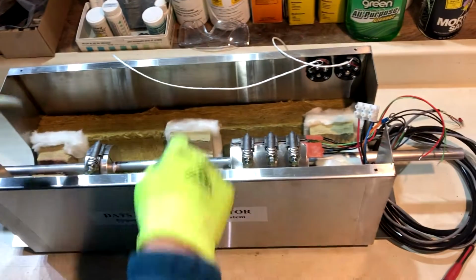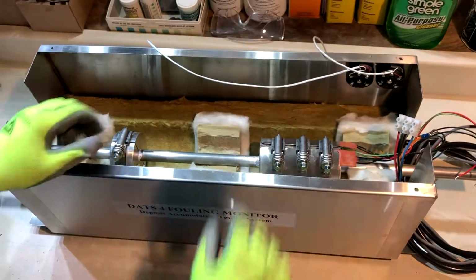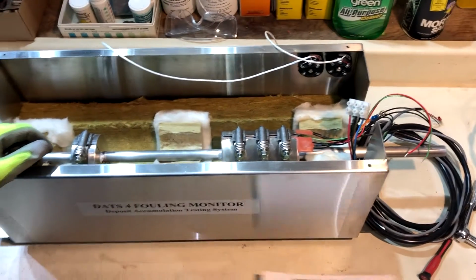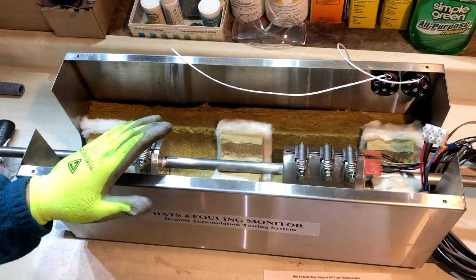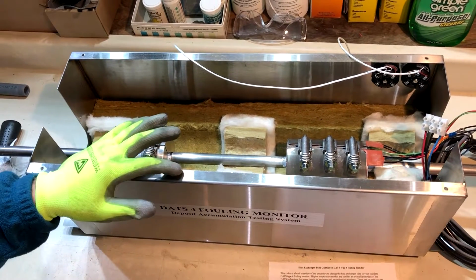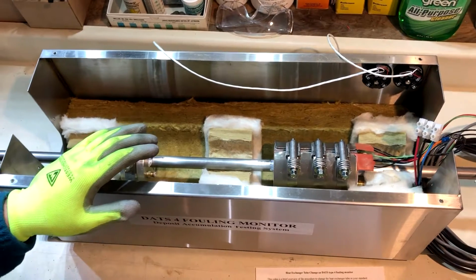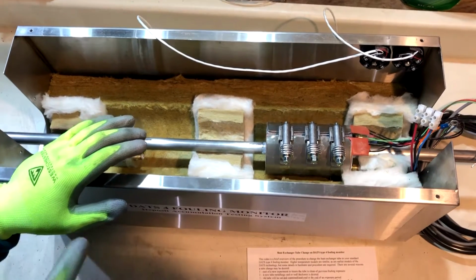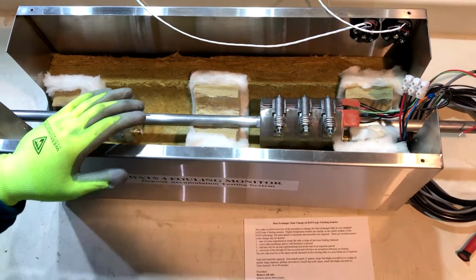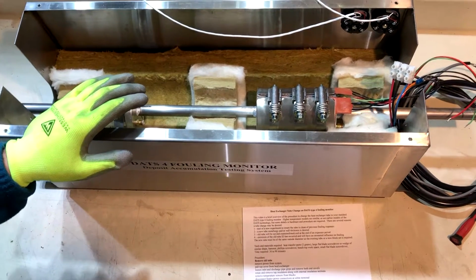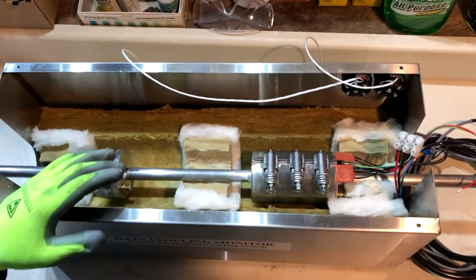process is the repeat of what we just did, taking it apart with the insulation placed back on top and rotated into place, the end covers, and then the top cover placed on. Then after that, put the system into service, get to your equilibrium flow velocity and heat flux, and zero the heat transfer resistance for your new tube so that your percent clean and your wall temperature will be accurate. And that's about it.